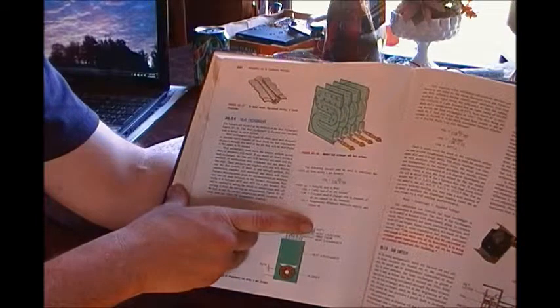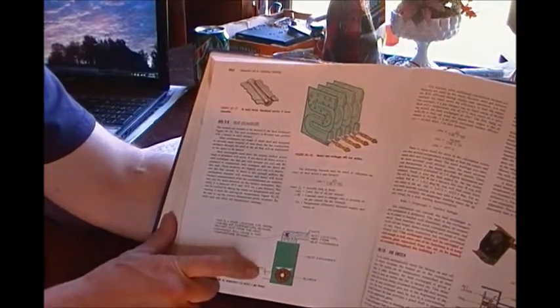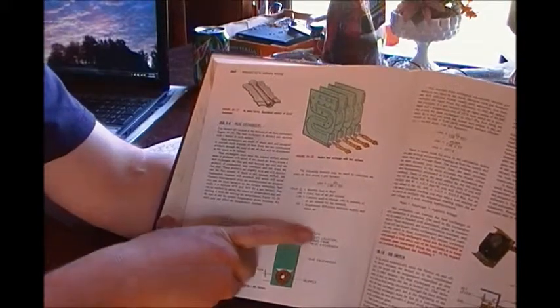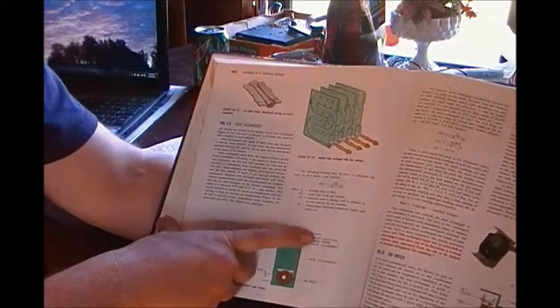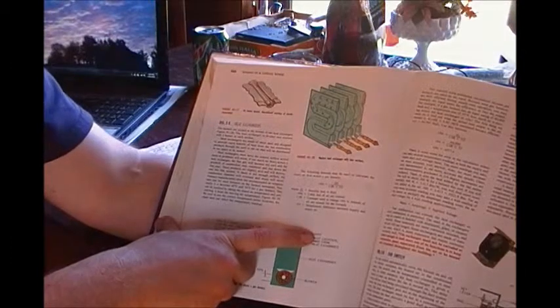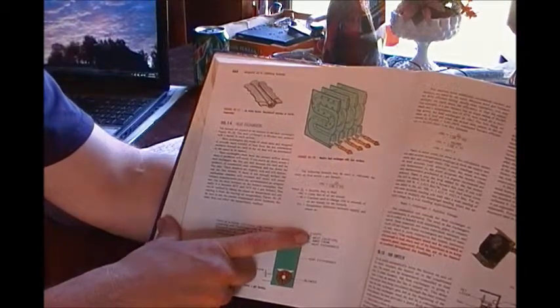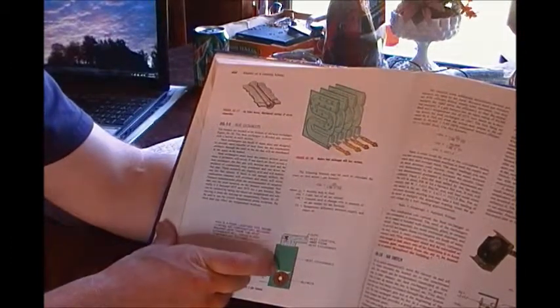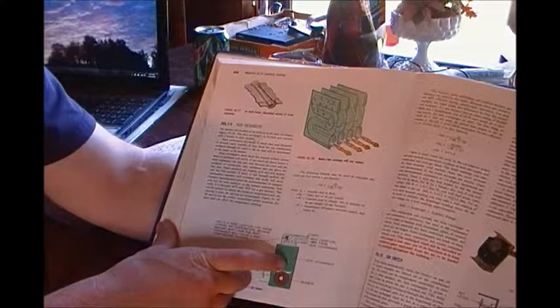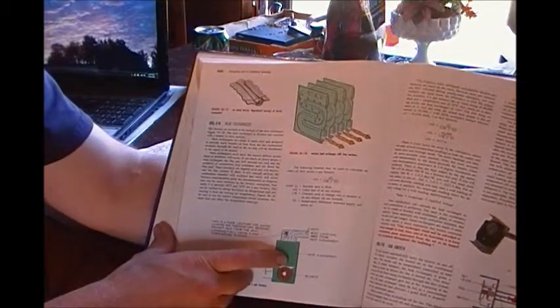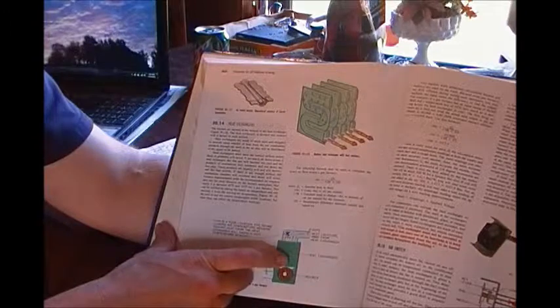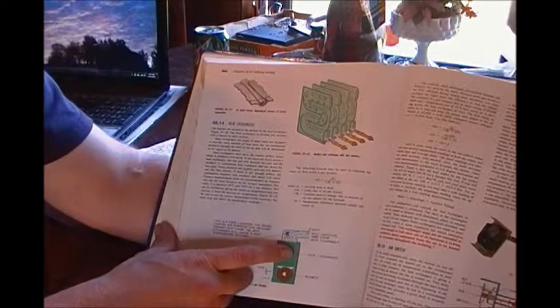The furnace is designed to run between 40 and 70 degrees difference. Meaning, if it's 70 coming in and 130 going out, it's within the 40 to 70 degrees difference. That's probably okay and will run just fine. If you start pushing it up to 70, then it could kill the life of that exchanger. So you want to keep it down a little bit. You don't want to exceed it, but you want to stay between 40 and 70.